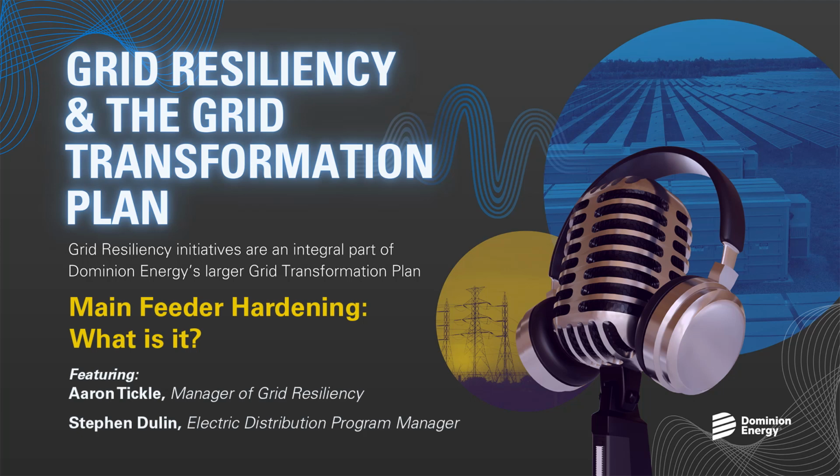So to accomplish this, we created new engineering standards, which account for higher wind and ice loads. And ultimately, these standards will aim to prevent poles from breaking when the storms do come through, or we have some other type of outage event. Ultimately, we won't be able to eliminate all the outages when the storms roll in. However, when we have a tree come down during a storm, we want the cross arms to fail before the pole fails, because these damages can be repaired much quicker than a broken pole can. So all of our main feeder hardening projects will be built to these new standards in the field.